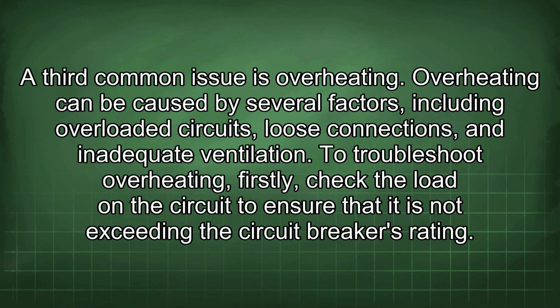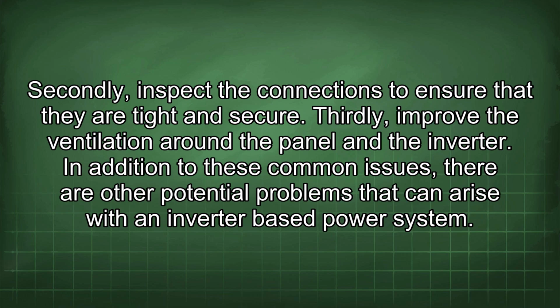A third common issue is overheating. Overheating can be caused by several factors, including overloaded circuits, loose connections, and inadequate ventilation. To troubleshoot overheating, firstly, check the load on the circuit to ensure that it is not exceeding the circuit breaker's rating. Secondly, inspect the connections to ensure that they are tight and secure. Thirdly, improve the ventilation around the panel and the inverter.